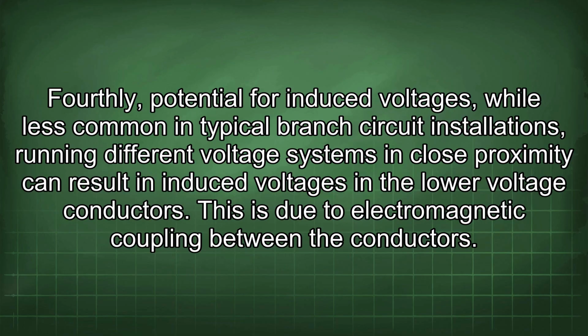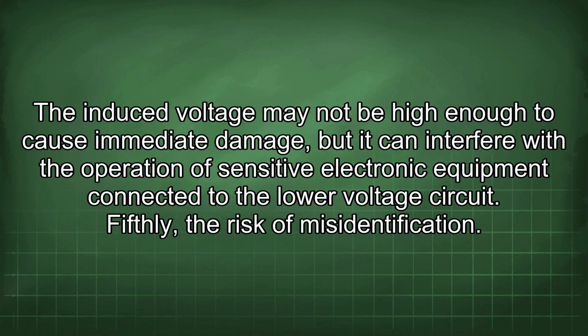Fourthly, potential for induced voltages. While less common in typical branch circuit installations, running different voltage systems in close proximity can result in induced voltages in the lower voltage conductors. This is due to electromagnetic coupling between the conductors. The induced voltage may not be high enough to cause immediate damage, but it can interfere with the operation of sensitive electronic equipment connected to the lower voltage circuit.